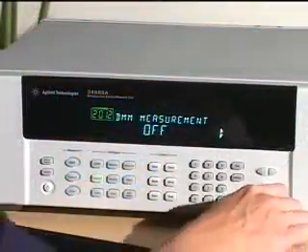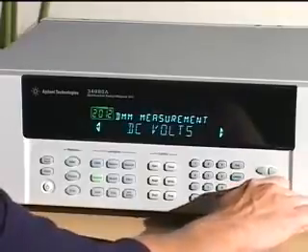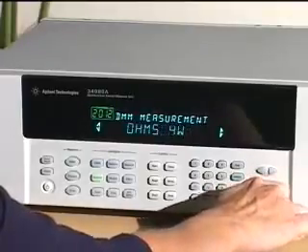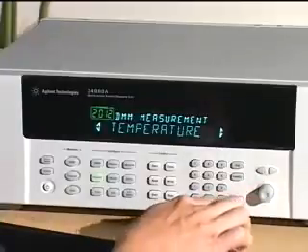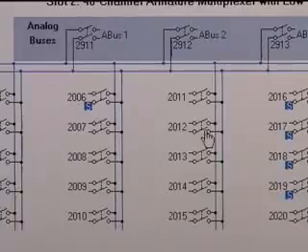We will configure the 34980A to measure several temperature points on our DUT, along with the input voltage and load. Each channel is easily configured from the front panel, a program such as LabVIEW or Visual Basic, via the web interface, or using Agilent's free IntuiLink software. For this demonstration, we will use the web interface to set up the channels.